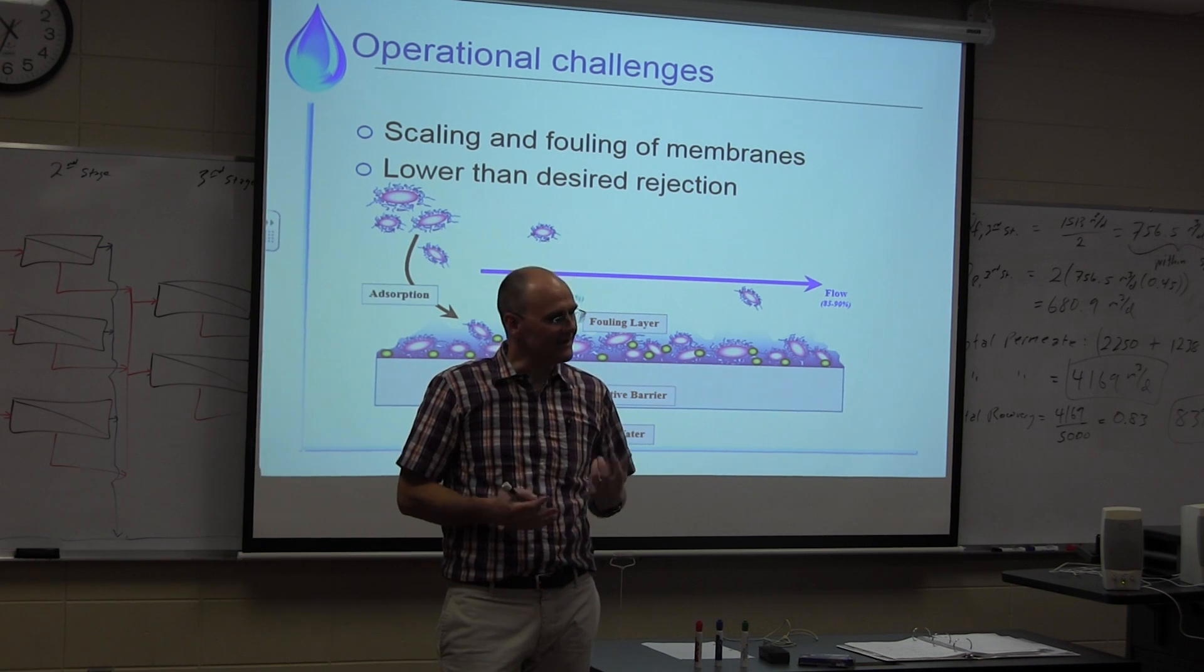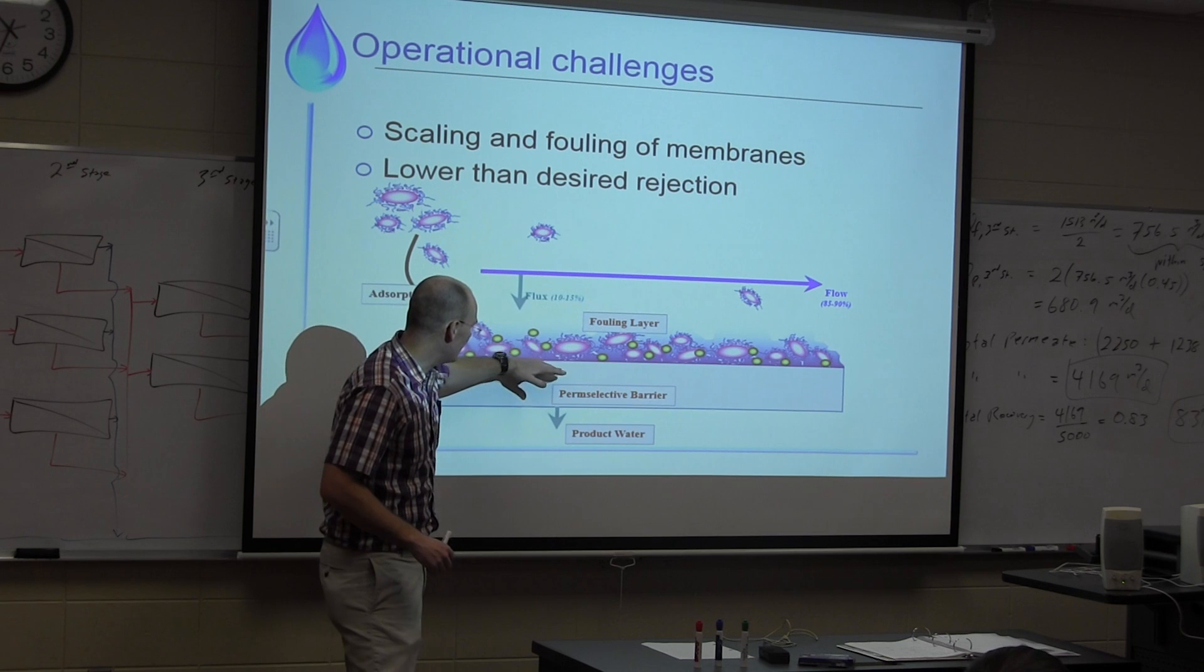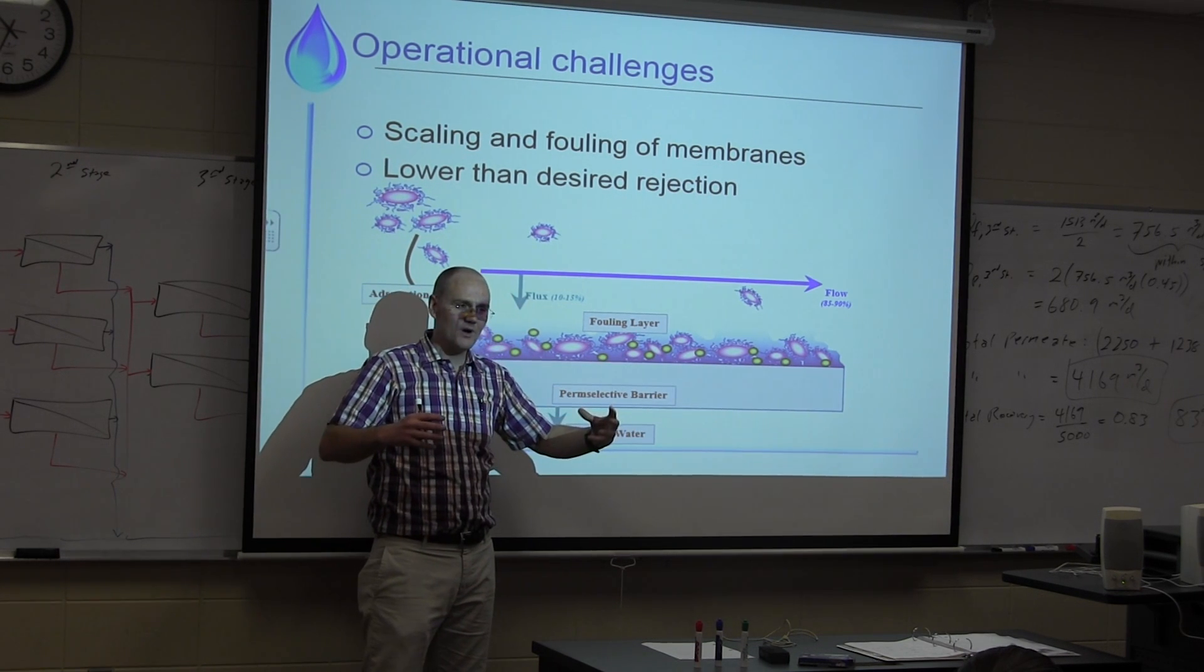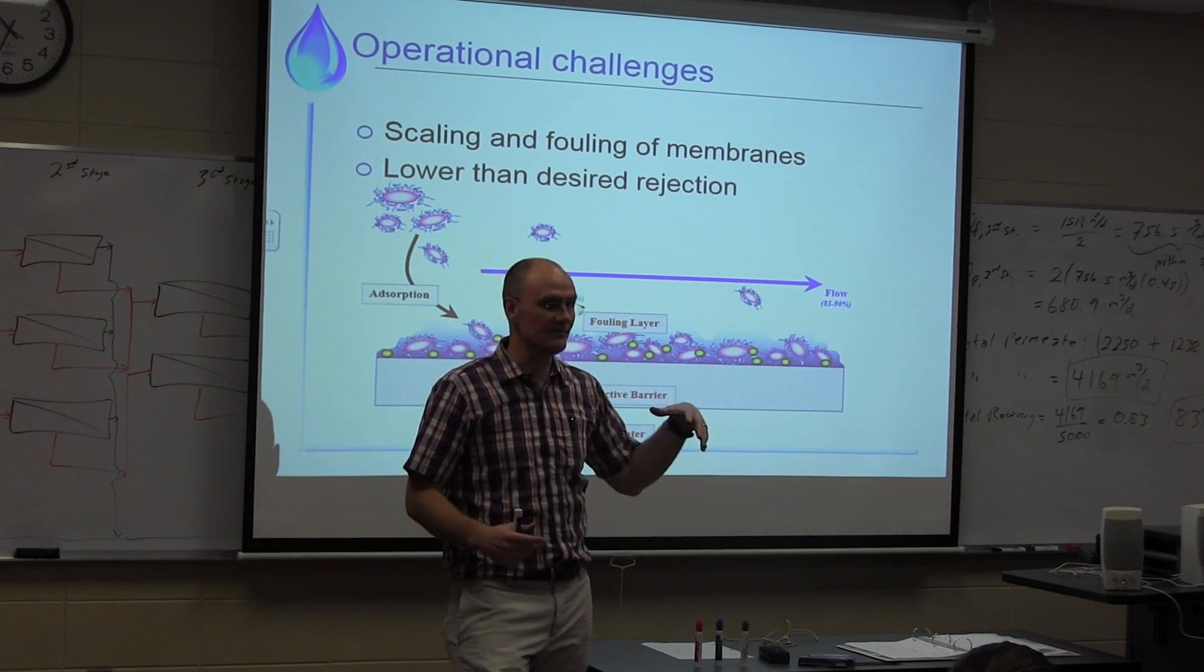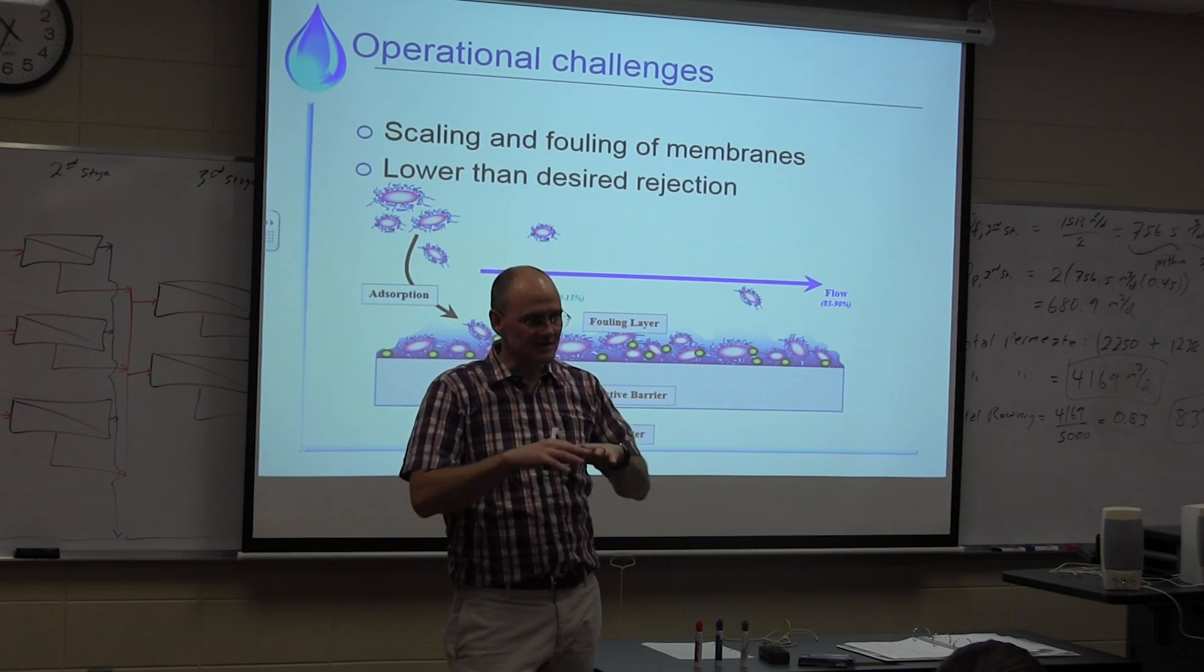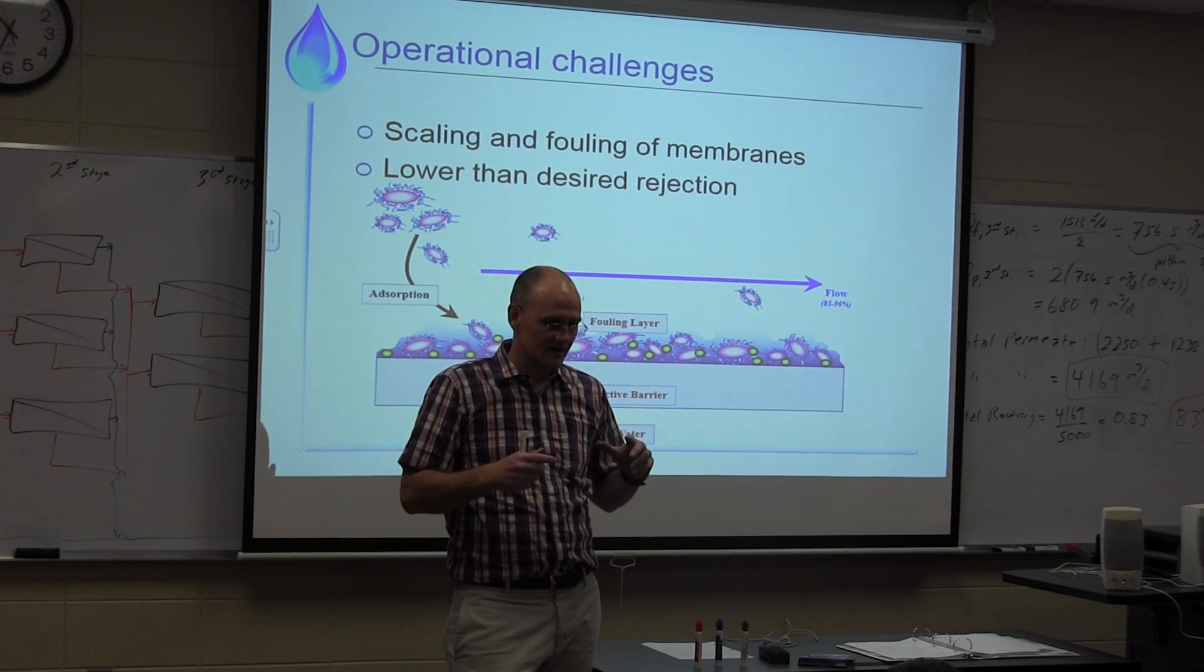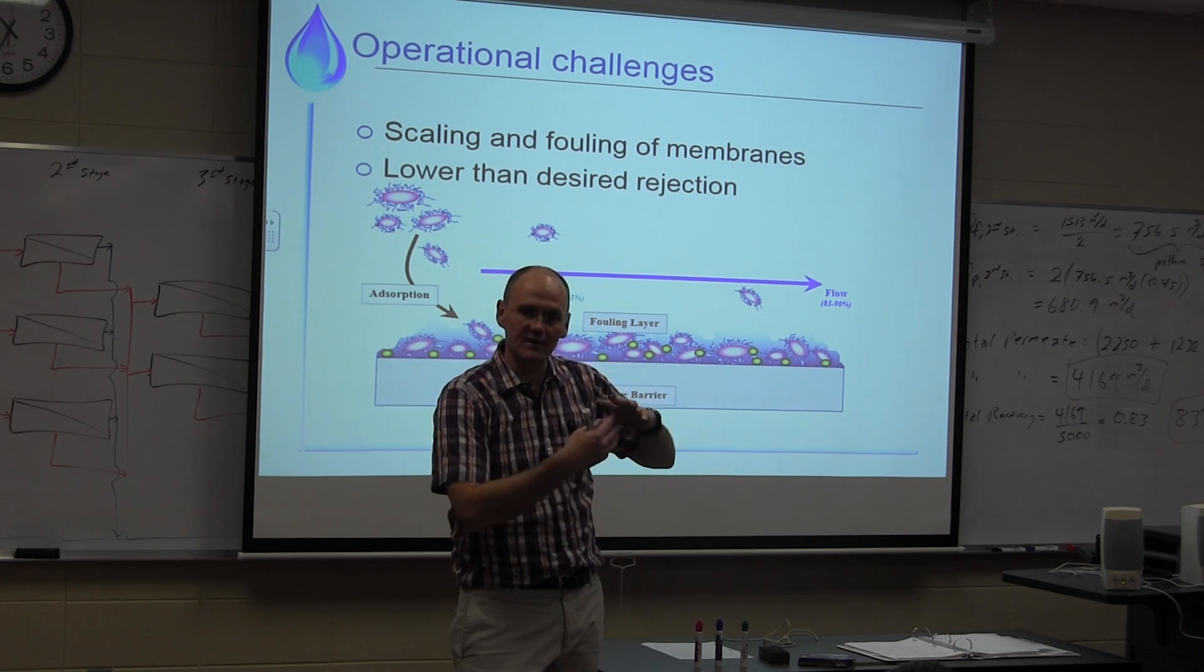NF and RO, you can't really do a backwash. One thing that we need to point out is that the membrane area required for RO and NF is much higher because our fluxes are much lower. And with such low fluxes, you can't really get a strong flow through the membrane that would wash something off.